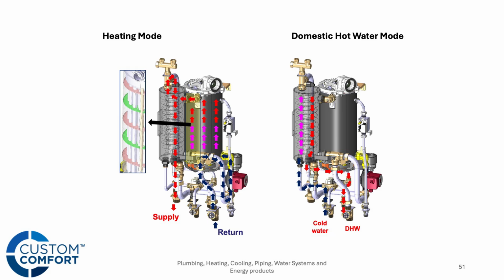This is a pretty cool view of how we're making your hydronic heat water for the house and/or domestic hot water for the house, right? It's just a good illustration as to what's going on inside that boiler, because there's a lot going on. So, cold water's coming in, being heated through the fire tube heat exchanger. In heating mode, it's just going to flow through that buffer tank, right? And out to the system.